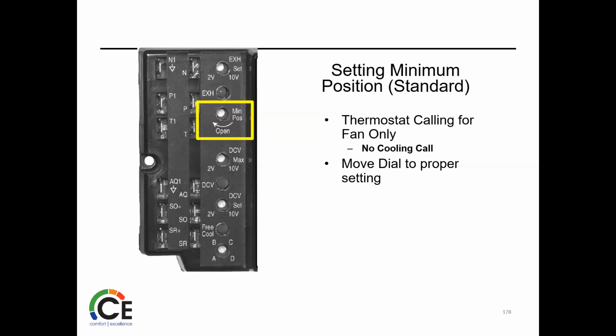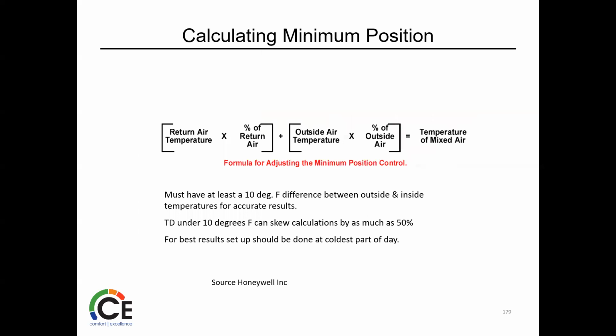Open is fully clockwise, fully closed is counterclockwise. There is a formula that you can use if you really want to dial this in. Most people just leave it at the defaults, which we'll talk about, but this will be in your packet too when I send it out. If you want to use it, you need at least a 10-degree difference between outside and inside air. So basically you have to have a load. You can't do it on a 70-degree day when it's 70 in the house or the building. A TD under 10 degrees can skew calculations. So again, we just need a load and a call.